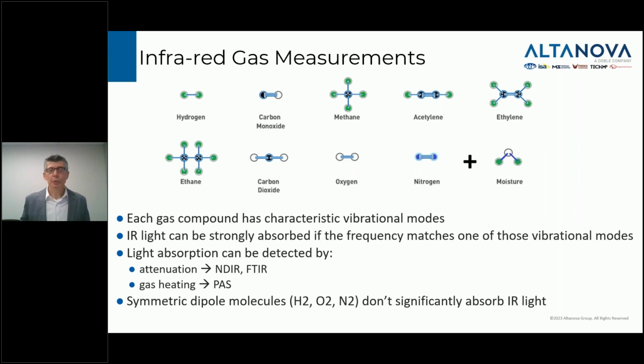And we can detect the absorption in 2 different ways. One is what I call attenuation. That is to say that if you have a light source on one side of the gas and you measure it some distance away, the intensity of the light diminishes as it's being absorbed by the gas. So you measure how the intensity is decreased or attenuated as the light passes through the gas. And the other way is that you can actually measure as the light gets absorbed by the molecule, there's a very small amount of heating. The light gets transformed eventually into heat. And so there's a technique for measuring that heating of the gas, which I'll talk about.